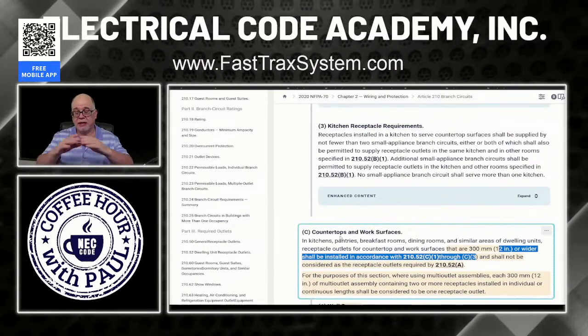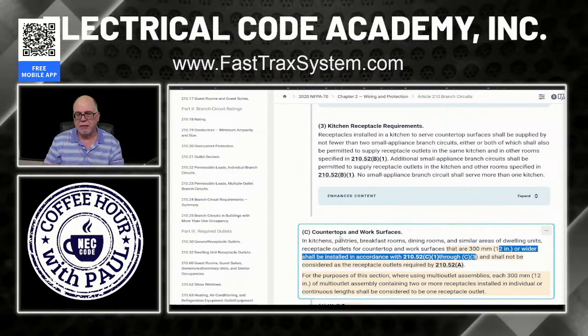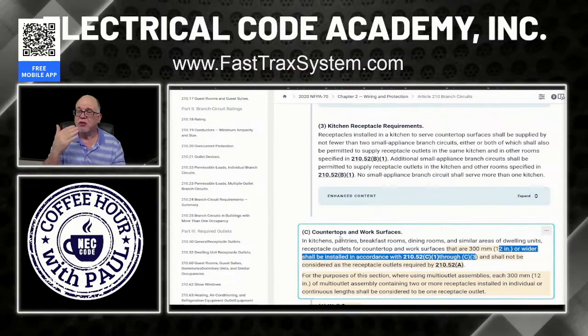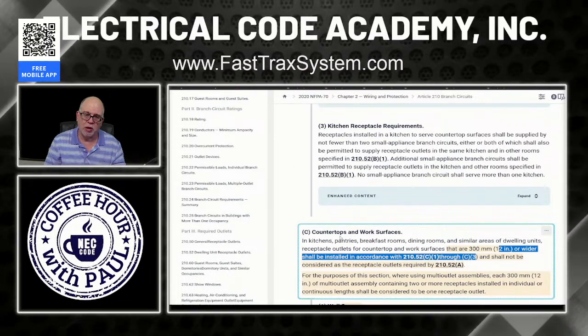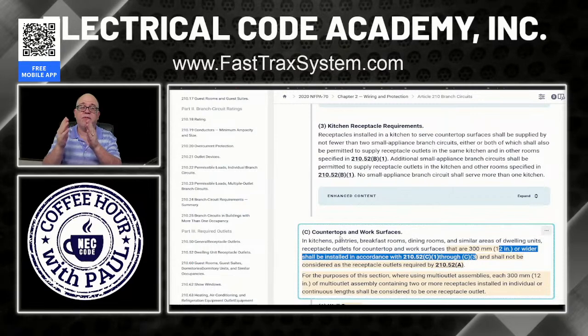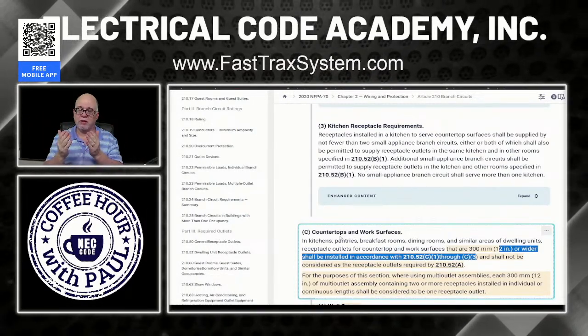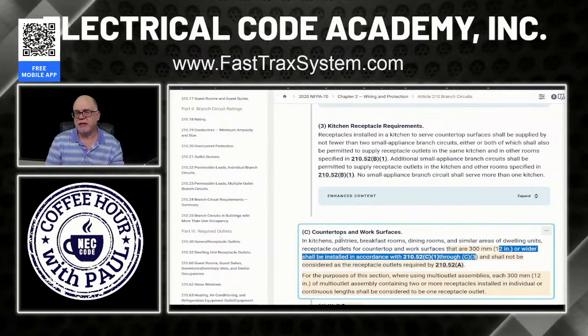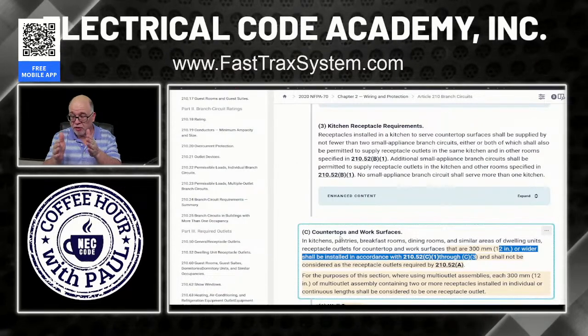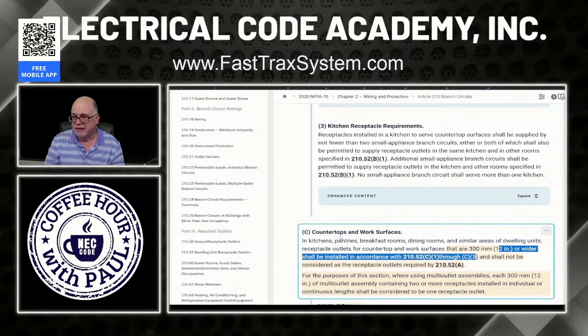Or you might put in a quad, and you have 4 receptacles, 2 duplexes mounted in a 2-gang box. And then one receptacle is one circuit, and the other receptacle is the other circuit. You still have to have at least 2 small appliance branch circuits there. And, of course, they can also serve all the other receptacles in the kitchen as well. But as far as serving the countertop, that would be fine. If the counter is at least 12 inches or greater, then I have to have a receptacle to serve that countertop.